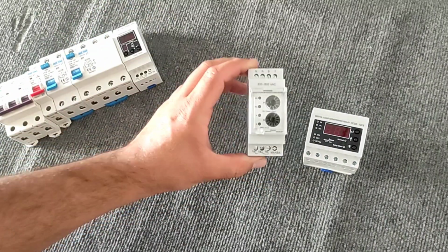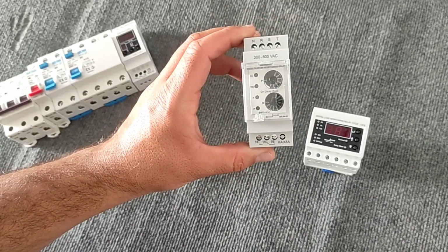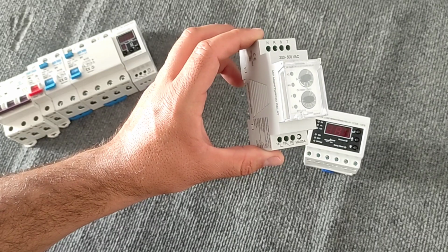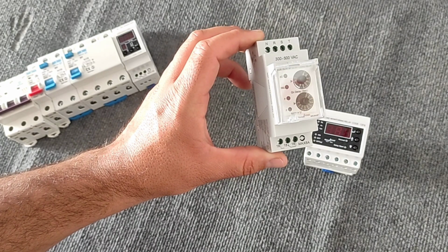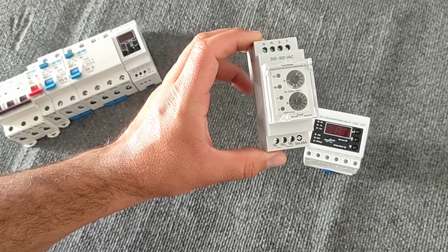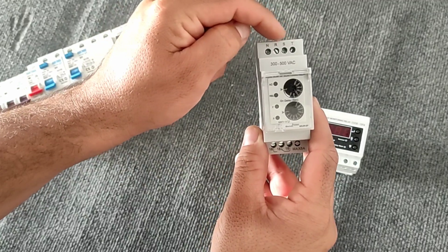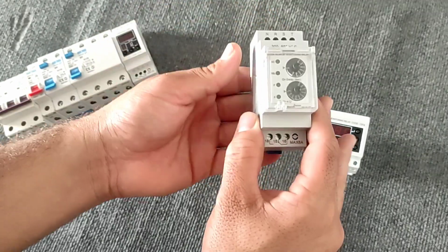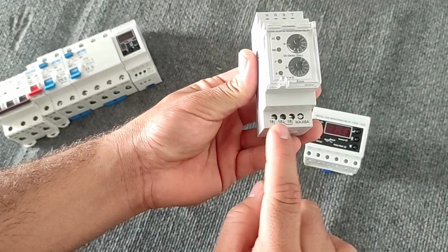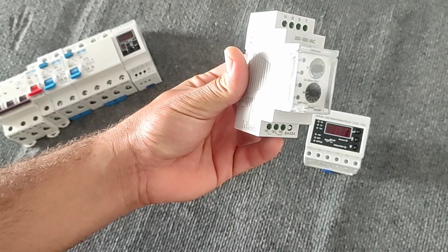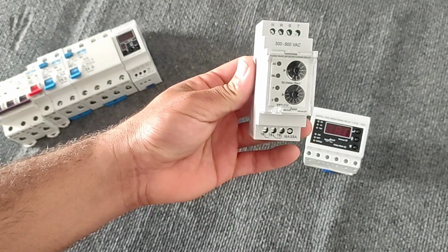The next relay is the three-phase monitoring relay. This relay is placed on the control circuit and protects three-phase consumers against two-phase conditions and increase or decrease of the electric voltage. Three-phase and neutral are connected to the upper part, and the lower part is the inputs and outputs of the relay. Every three-phase consumer must be equipped with this relay.